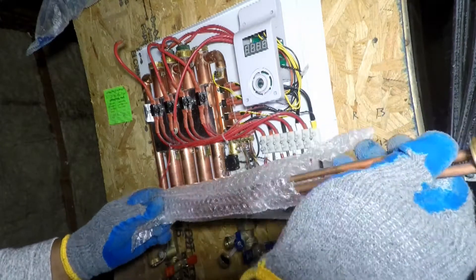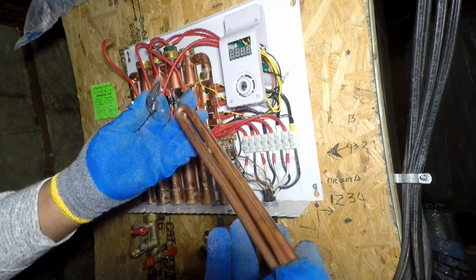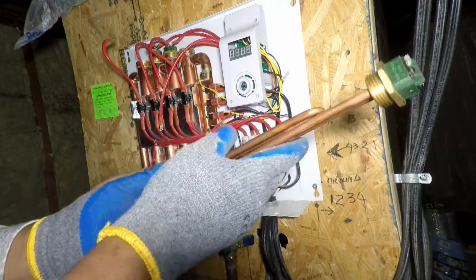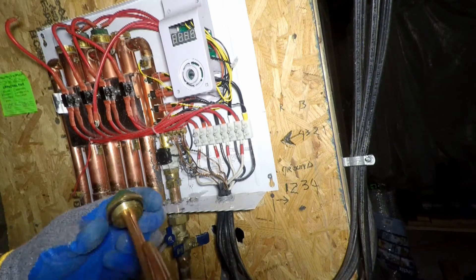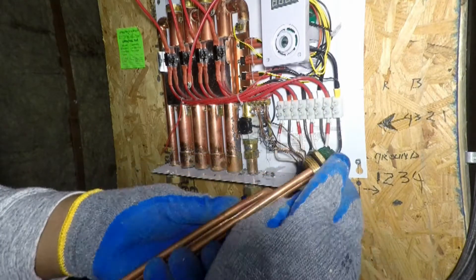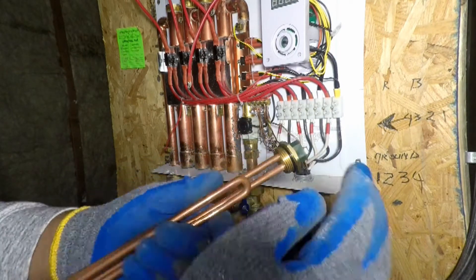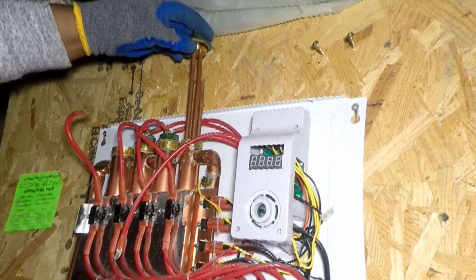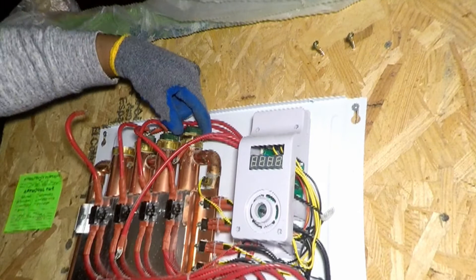This is the brand new heat element. It comes with an O-ring, but the O-ring is not pre-installed. The O-ring is placed into position on the heat element. Before installing, the O-ring is lubricated with water. The heat element then goes into heat exchanger L1.